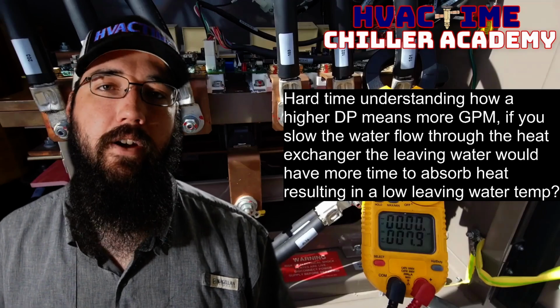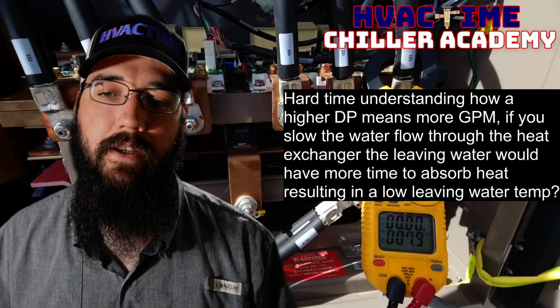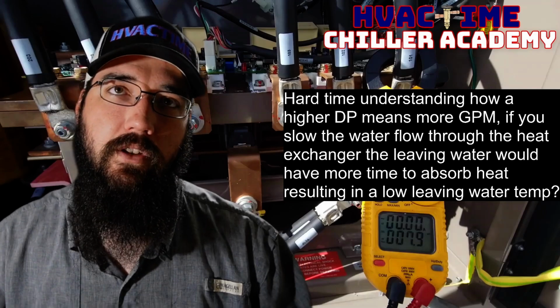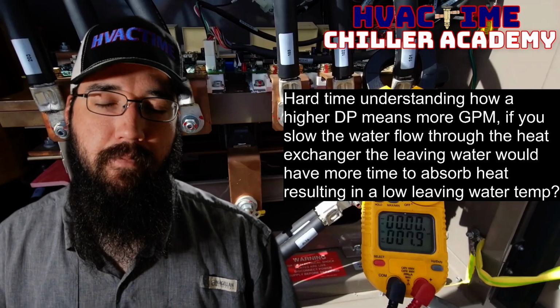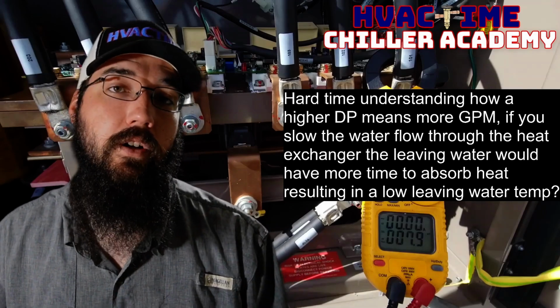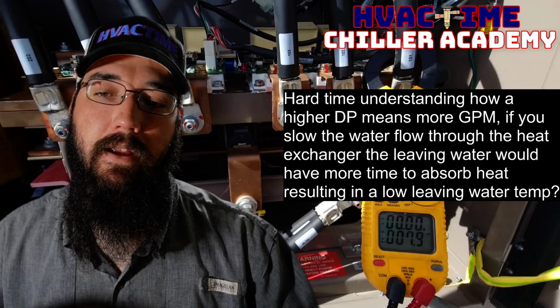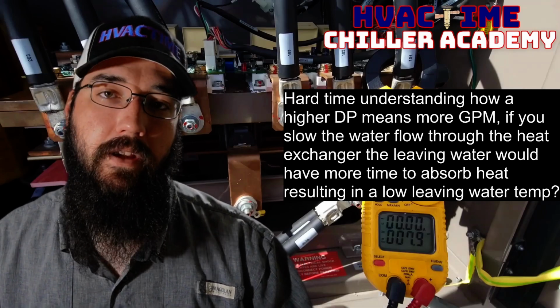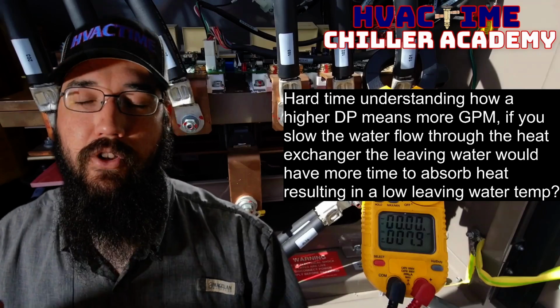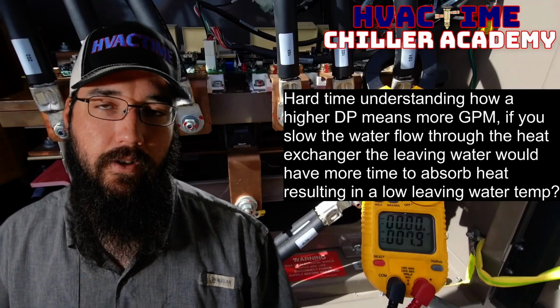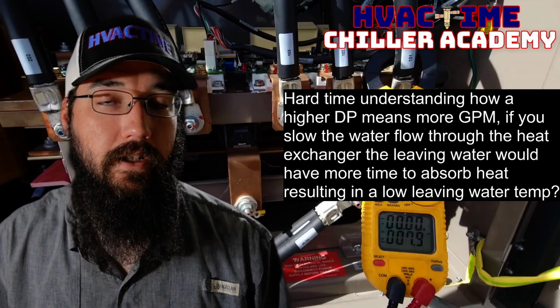All right. And there's a lot of acronyms. That's one of the things that we need to be very mindful of. If we slow down the GPM, then we will end up having a higher TD because we can pull heat out of the water easier, which makes it easier to hit leaving water set point.